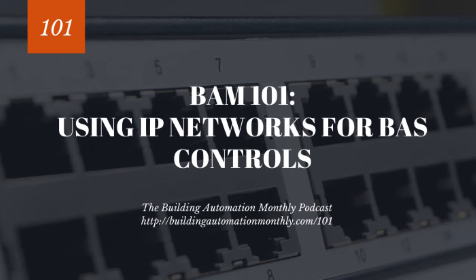You mentioned fault tolerance. What is that for those who don't know what it means? Fault tolerance is a method of how successful or reliable your network is. I always go back to MSTP because it's one of my major pain points. When you connect these controllers together, it's strip the wire, plug it in, walk away, go to the next one. What I mean by not very fault tolerant is if a little bit of wire is showing and it's grounded, or part of the wire touches the other side of the communication, your network goes down or it's very inconsistent. When these problems happen, they're very difficult to troubleshoot, to the point where you have to disconnect the network at multiple points to find out where the problem is.